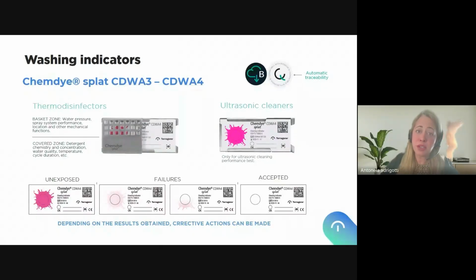On the thermal disinfection side, we see that we have a configuration on top to protect the indicator. Because what we want is to simulate what actually happens with the instruments inside the chamber. Not all items will be impinged or reached by the water spray. So we want to check that this is true also for the indicator. And if the indicator can be correctly washed out, it means that those instruments that have the same situation will also be cleaned.